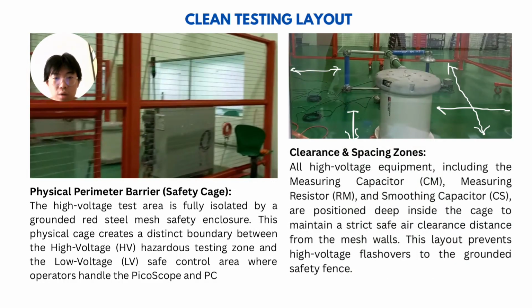And this is the clean testing layout. It has two parts: the physical perimeter barrier, safety cage, and the clearance and spacing zone. For the physical perimeter barrier, the high voltage test area is fully isolated by a grounded steel mesh safety enclosure. This physical cage creates a distinct boundary between the high voltage hazardous testing zone and the low voltage safe control area, where the operator handles the picoscope and PC.